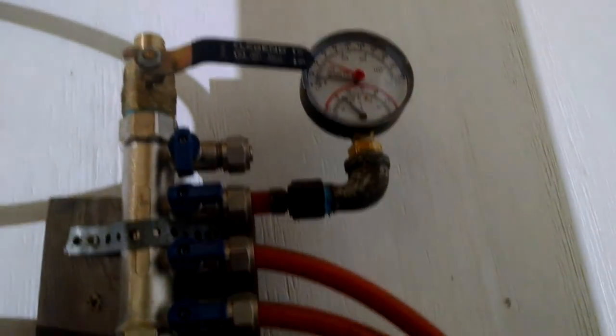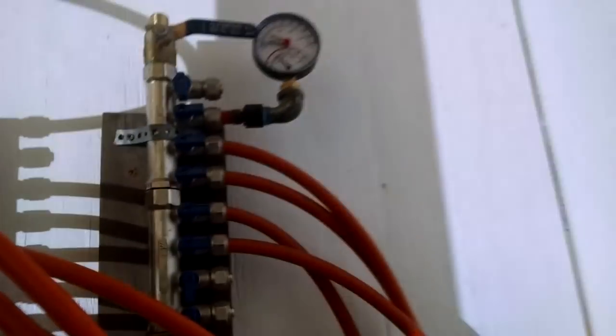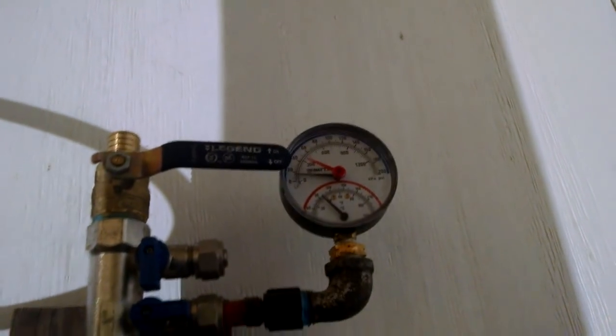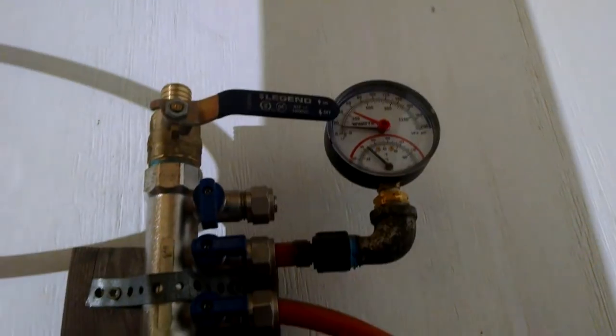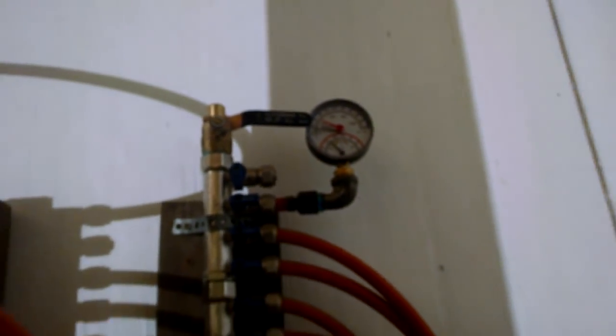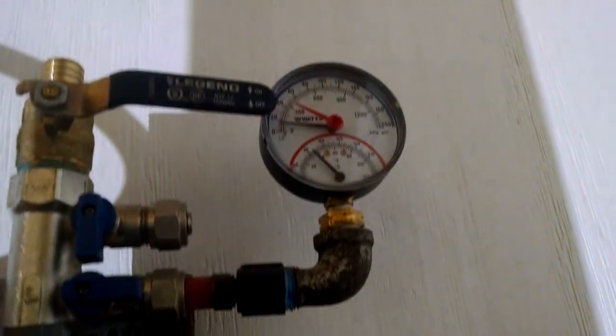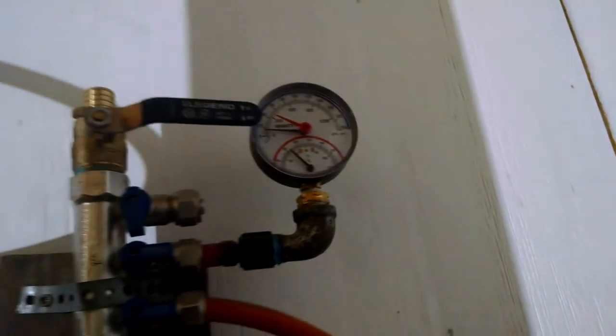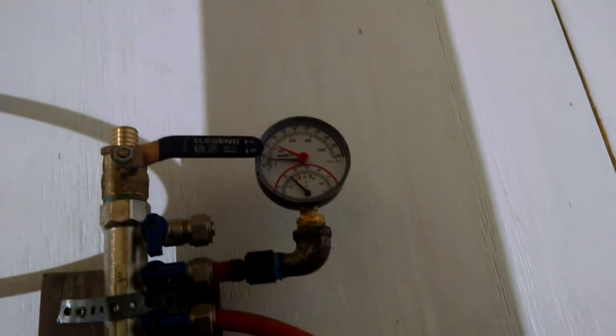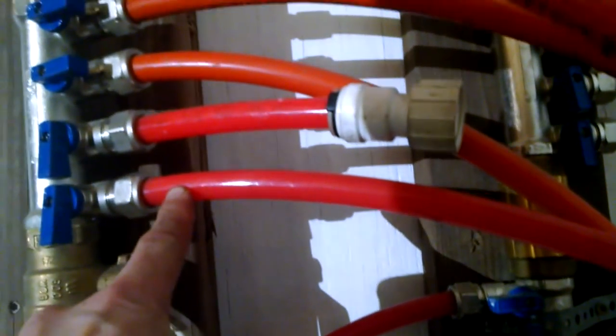Now you see our system here, that temperature pressure gauge is off to the side of the system. That's the forward line here. It won't read temperature correctly because it's a little bit out of the mainstream of the water. It's basically touching the water stream. It's not really sensing the full temperature of the system. So right now, for example, we're reading only about 100 Fahrenheit. It's probably more like 130, 140.